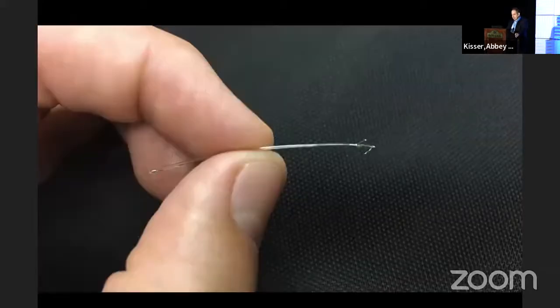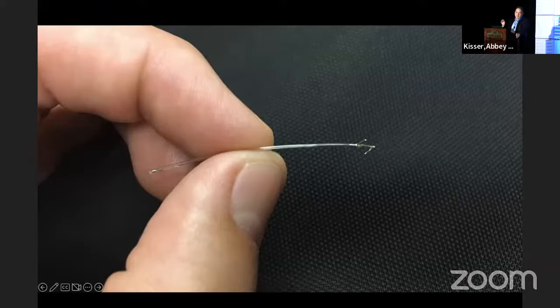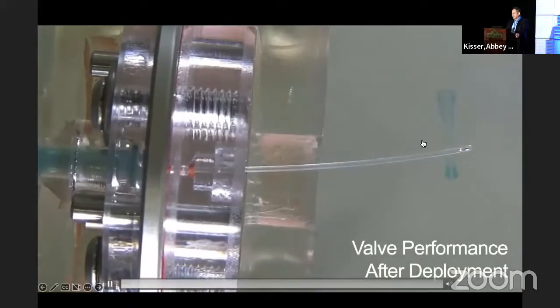And this is what it looks like live. It's a very small device. It's a 0.016 lumen, and you'd think that's very small, but actually because of the short distance and the small size, there's very little resistance to the flow. This is seeing the valve in action. You have a high pressure in the CSF, which you see here in blue.